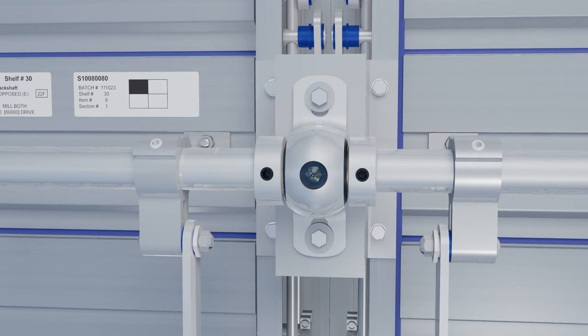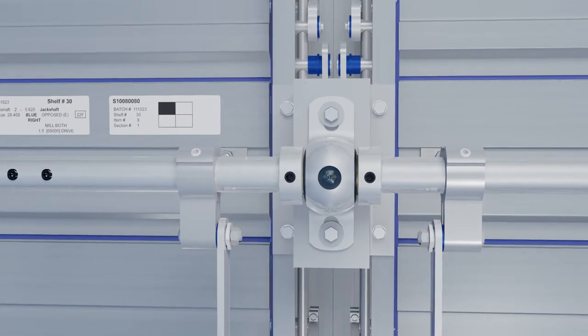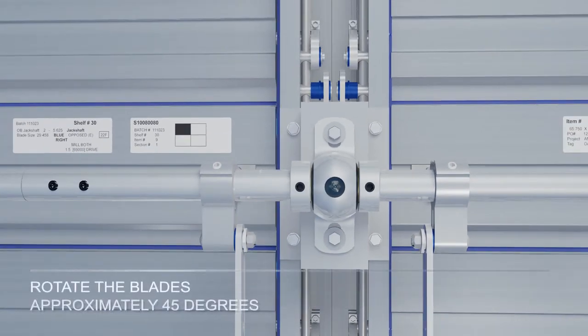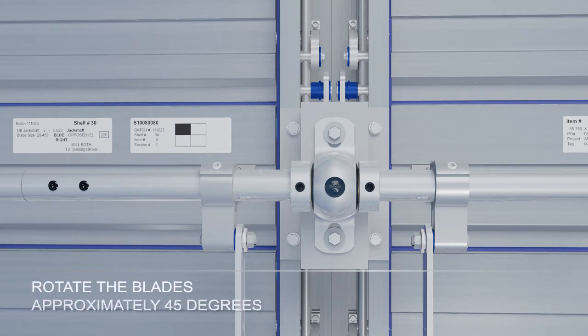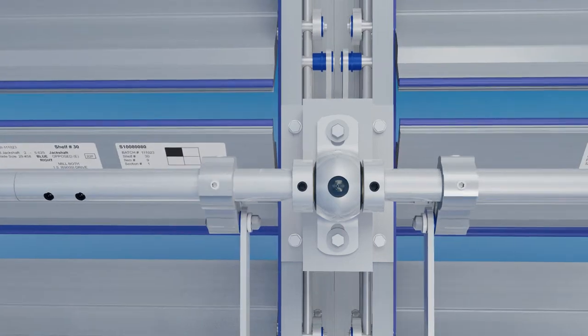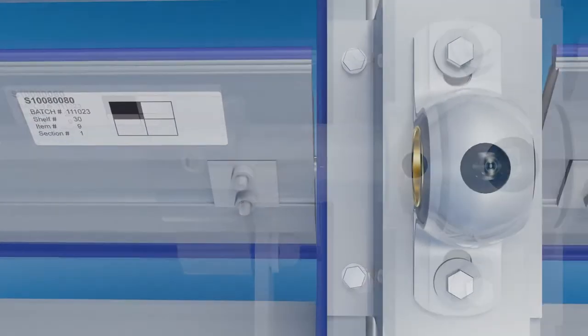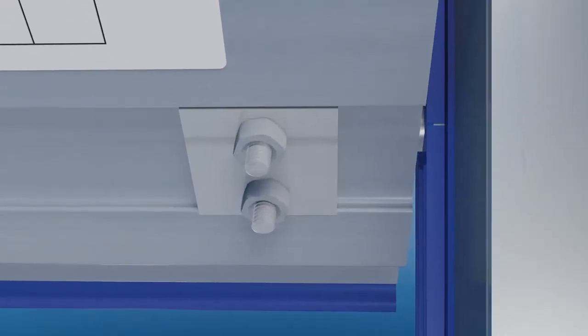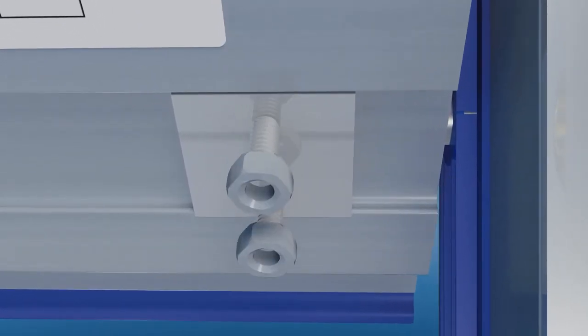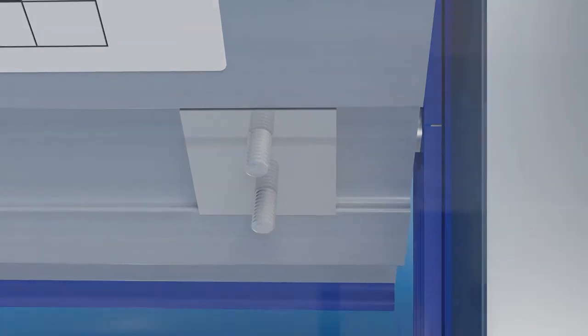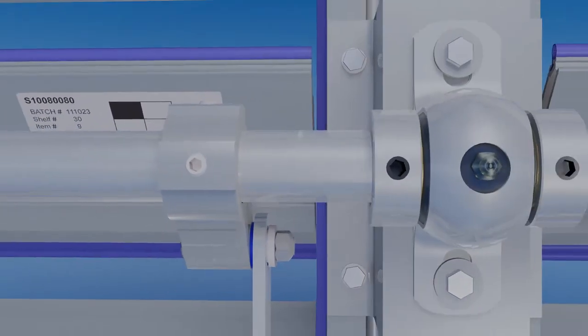To connect the blade clips to the damper drive blades, rotate the blades of both sections so they are open to approximately 45 degrees. Then, loosen and remove the U-bolt hex nuts located on the front of both damper drive blades.